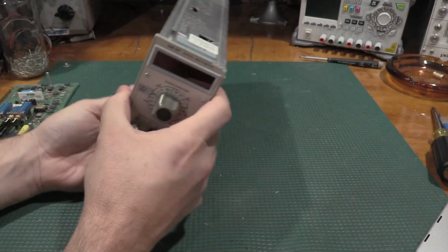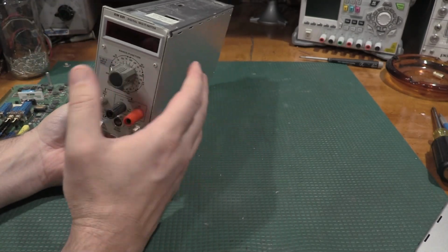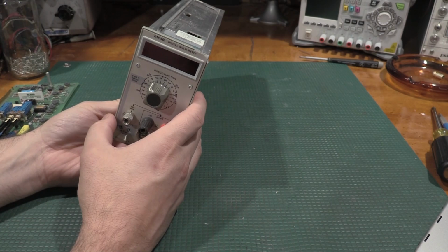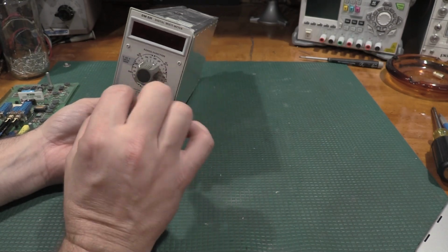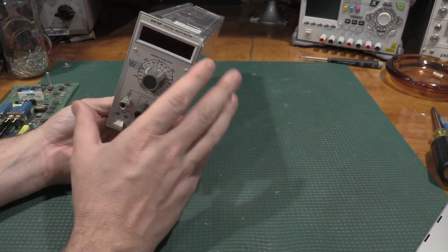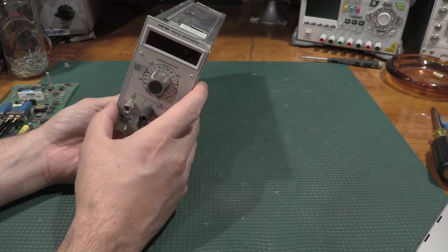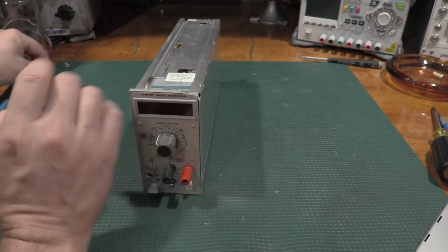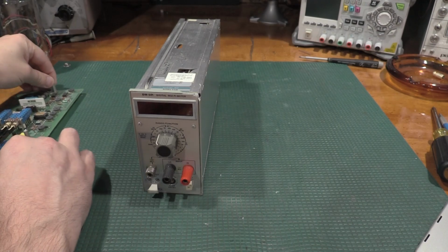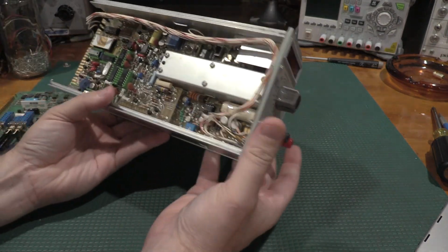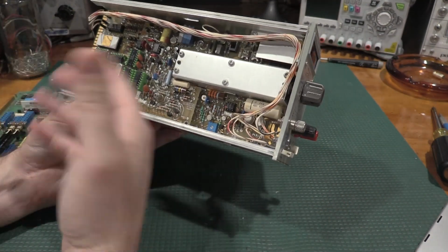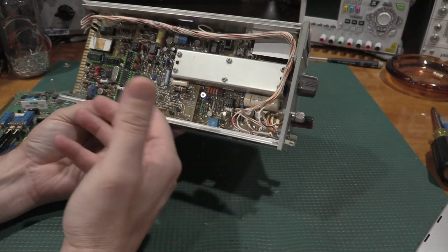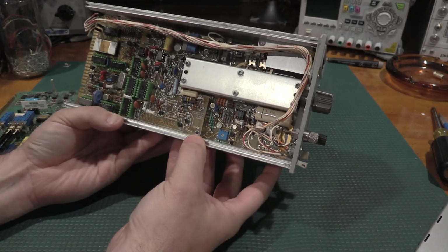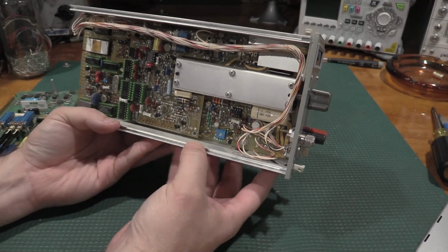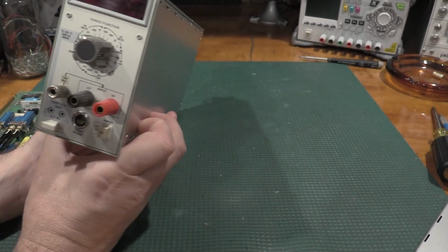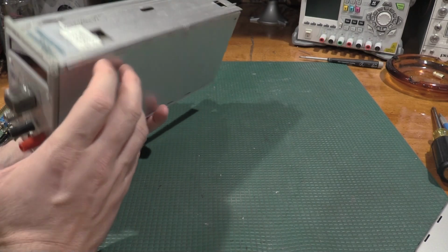These meters, all of them, I've done a bunch. They typically calibrate pretty well. I very rarely have a couple that completely fail calibration and need some repairs, this being one of the only ones that's done that. And I've got 6. I've done some for other people and things like that. So pretty good repairability and track record on these meters. So not bad units to pick up.